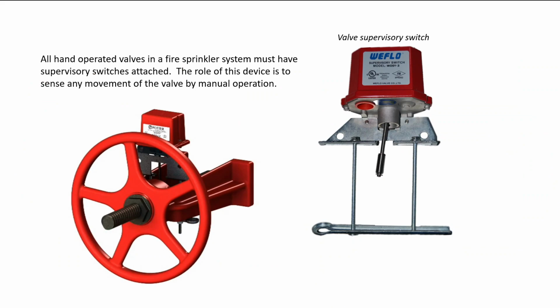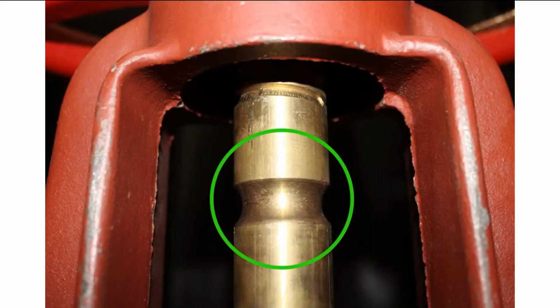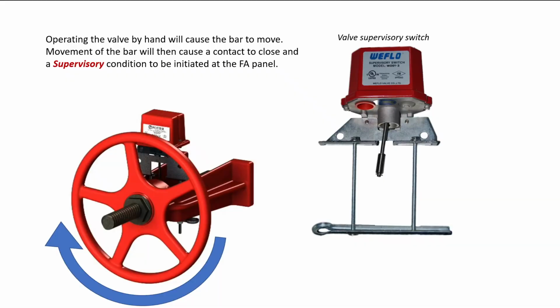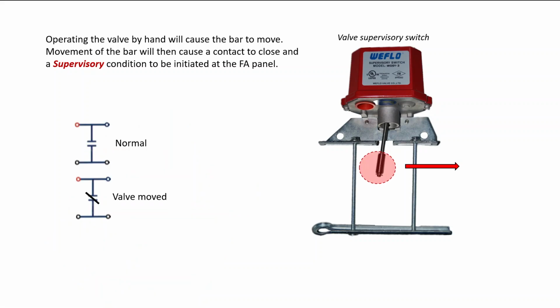If we take a look at a hand-operated valve, a standard form is one with a stem that moves in and out on threads as the wheel is rotated. The role of this device shown here is to sense any movement of the valve by manual operation. If we take a look at the stem of this valve, we'll notice that it will have a groove ground into it by the manufacturer. When the valve is operated, this stem will move in a linear fashion, up and down. And because we have this pendulum sort of object rod here mounted in the middle of the valve, this rod will then move when the wheel is rotated because the stem will move in and out. Once it does, it'll cause this to move, and that will then trigger a set of contacts to operate, sending a signal to the fire alarm panel.